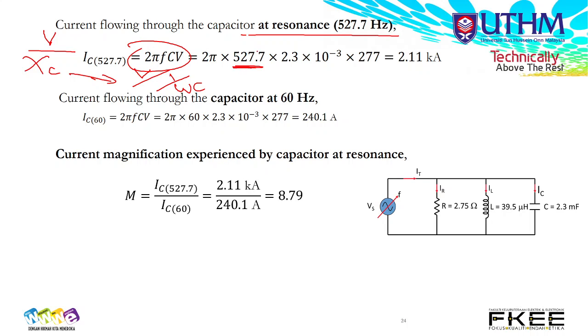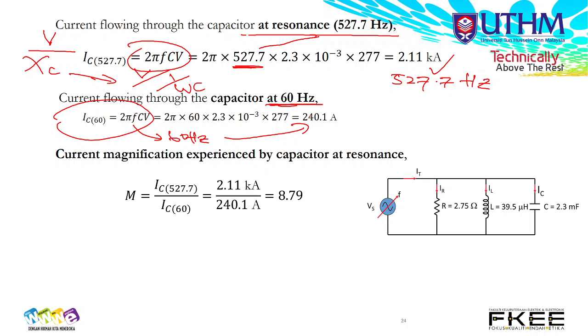If we look at the current flowing through the capacitor at 60 Hz versus at 527.7 Hz: at 60 Hz, the current is 2 pi FC with F at 60 Hz, so the current is 240 amperes - this is the fundamental current under normal conditions without harmonics.